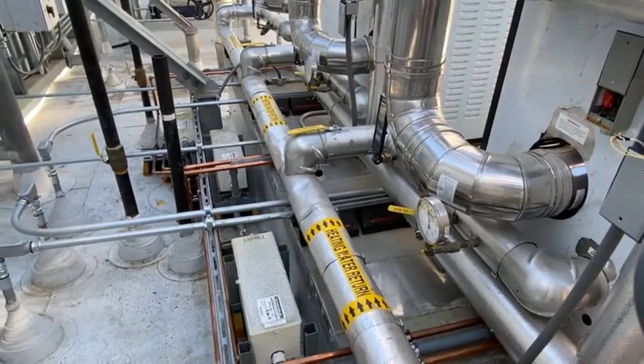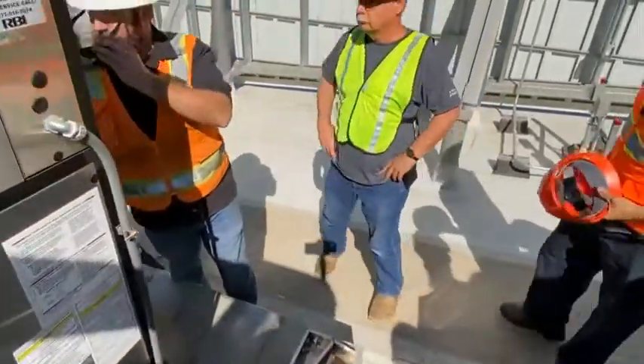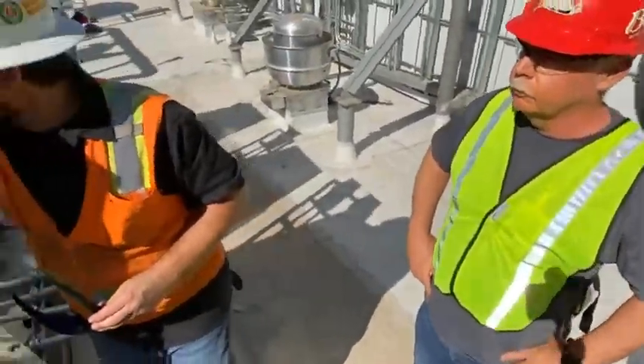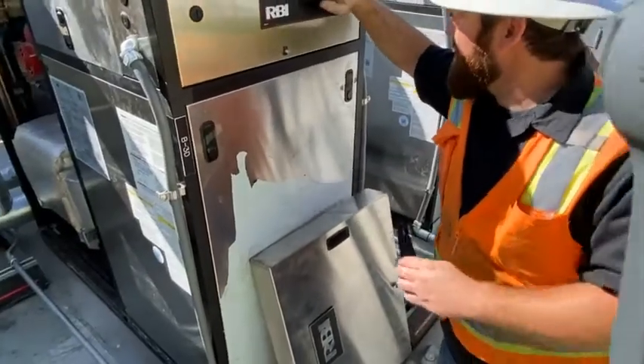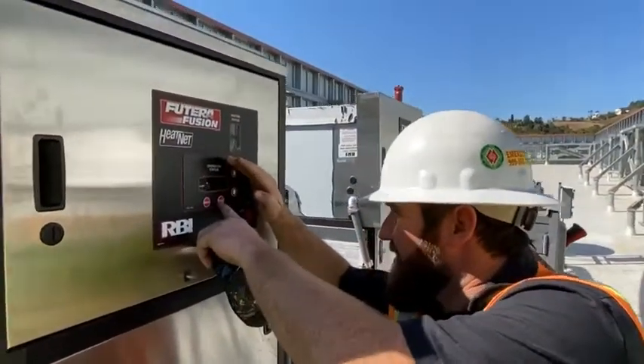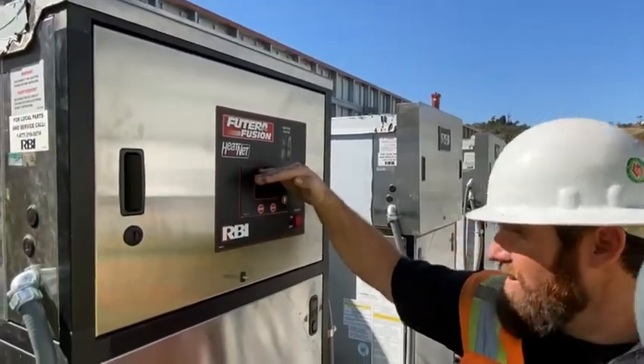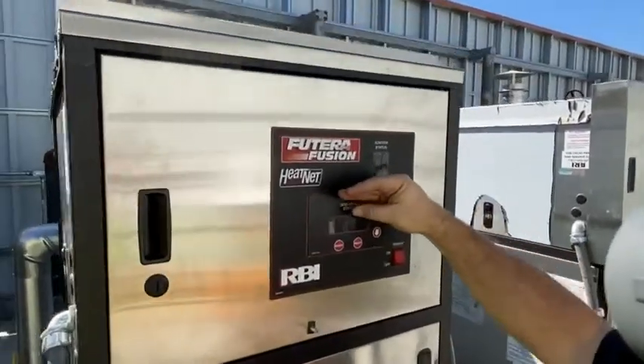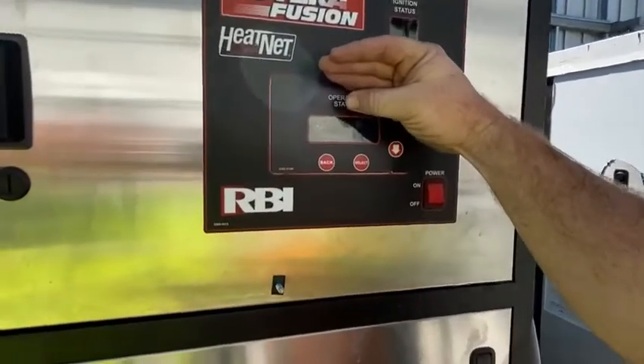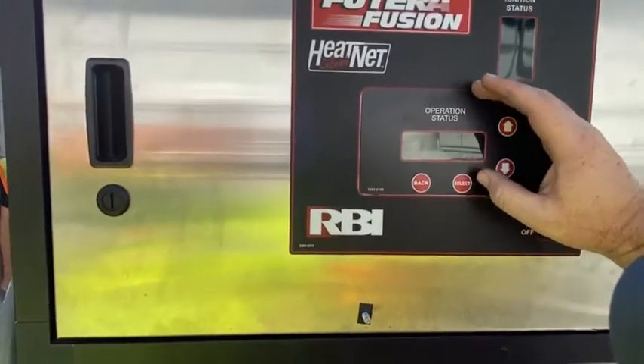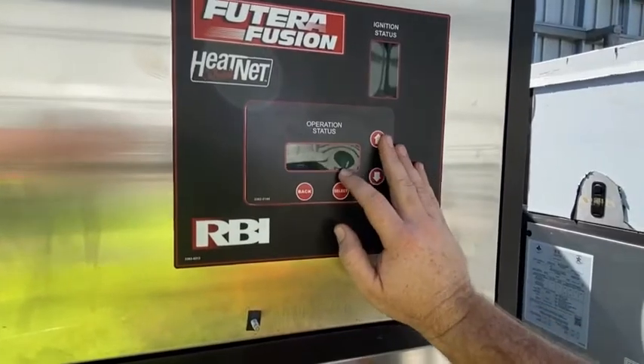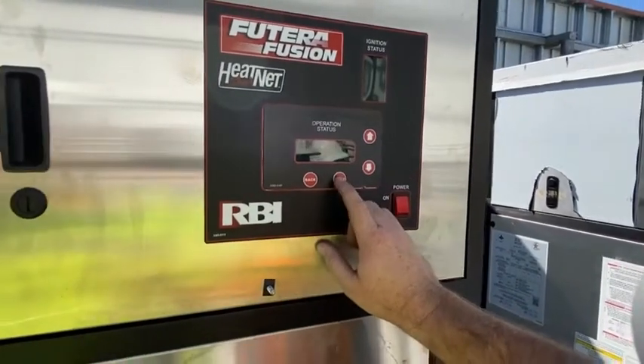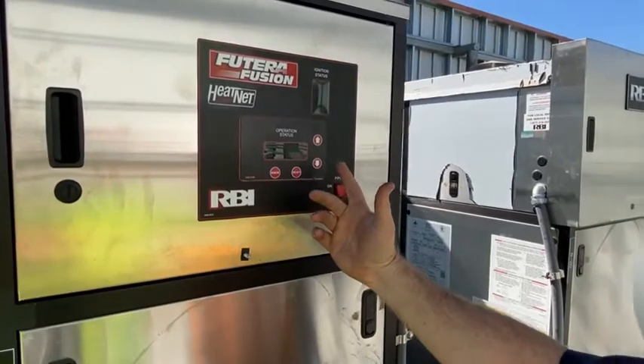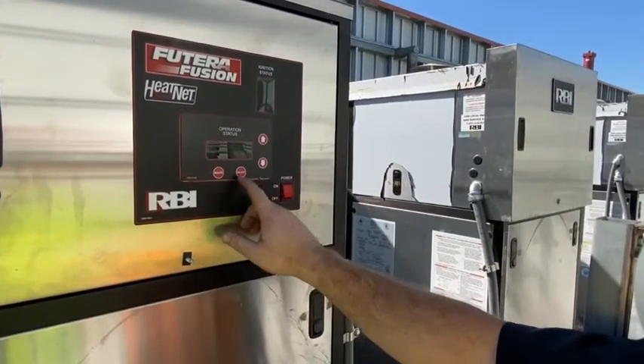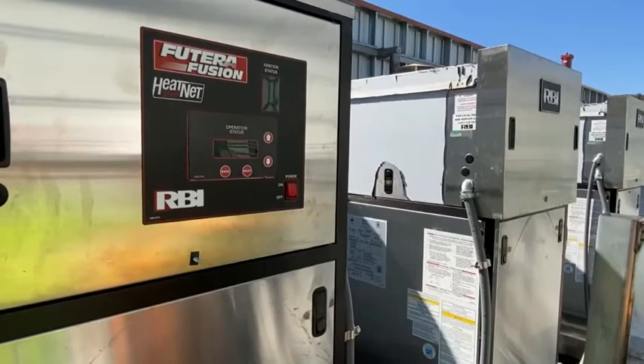You need to adjust both set points. So you said they're 140? This one's set at 150 at the moment. Wow, that's kind of low, isn't it? Okay, it says running at 57% right now, so it's modulating down. And then it says system set. That's the 150, our set point. All you have to do is hit select. It starts blinking, then you adjust up or down, and hit select again to set the set point. It's very simple.